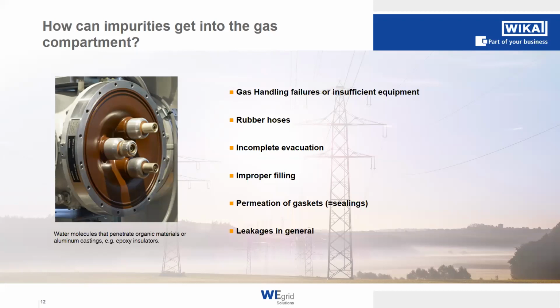So the O-rings, for example, as shown in the picture on the left. Epoxy insulators, over time they get porous, and the humidity can find its way into our gas compartments. Or of course leakages in general, like destroyed valves, or not locking the hose correctly to its connection. All that could cause humidity to get into the gas compartment.